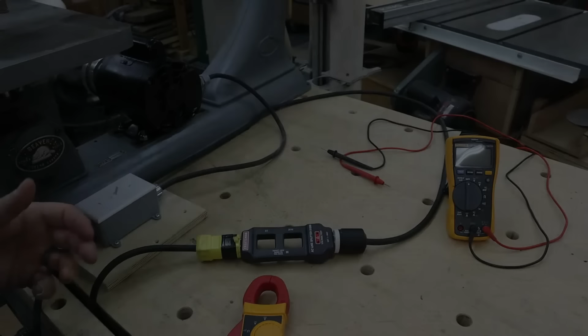Now, the first thing we're going to do is energize the motor. I've disconnected the belt in order to lower the noise during filming. I'm going to turn on my ammeter for AC current, and we're going to take a reading here. I'm going to get an actual value, and I'm getting about 5.02 amps. So I am going to hold, and we're going to lock that value in.